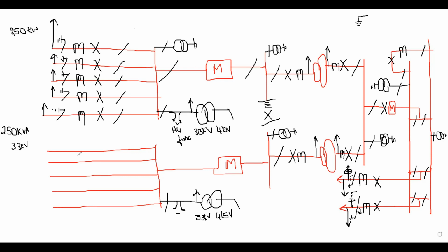So that is the representation of the single line diagram. Generally, this is my way of design. You can have designations on your own. In my projects, what I generally consider is letter A for 400 kV, letter B for 220 kV, letter C for 132 kV, letter D for 33 kV. It's just my representation. You can have D for 400 kV or 1, 2, 3, 4, whatever it may be. You can choose. So I am considering B and D.